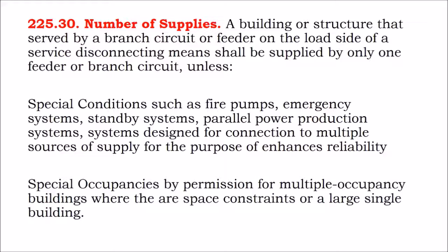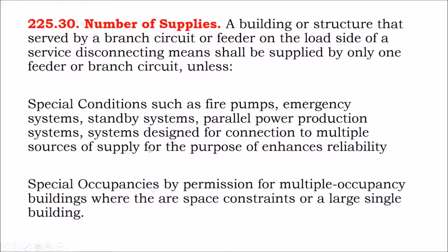So what that says is you should not have two utility services feeding the same building for no reason. Just because you want power on that side of the building and the other side of the building. The building has to have the one supply unless there's a special reason or special condition for it to have two.